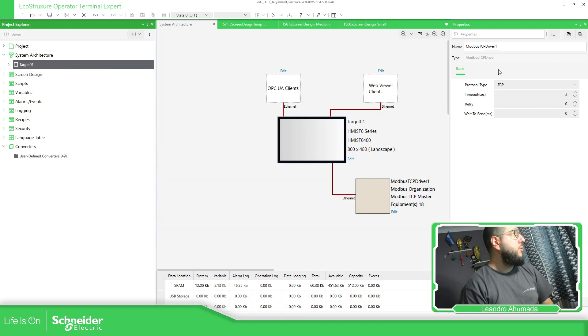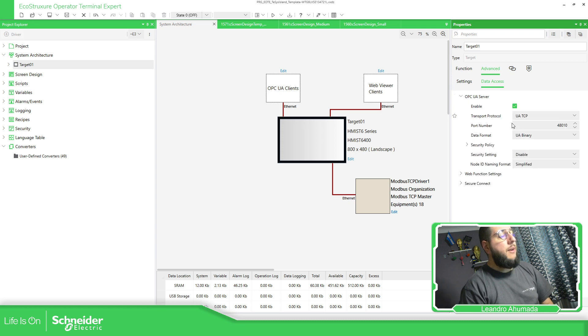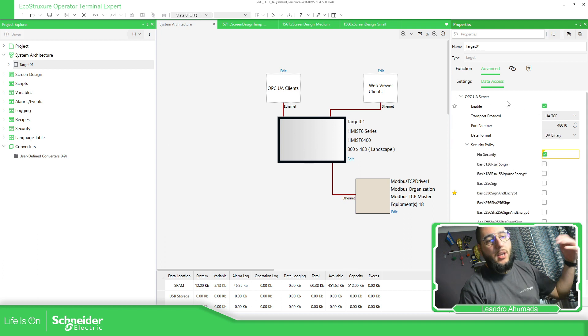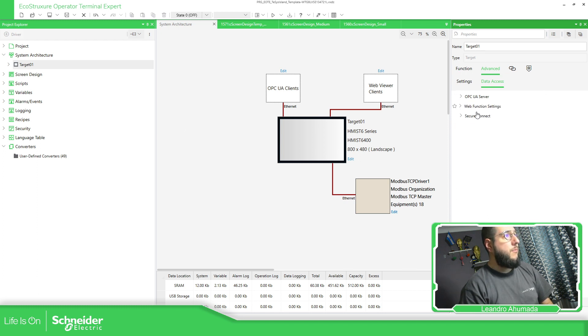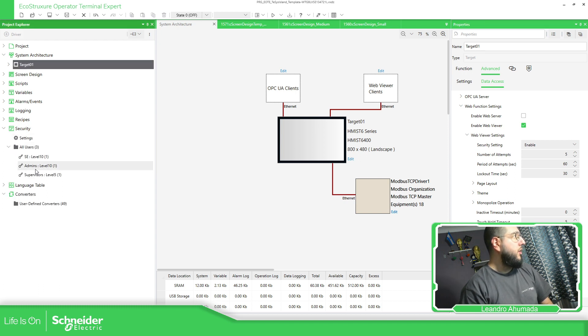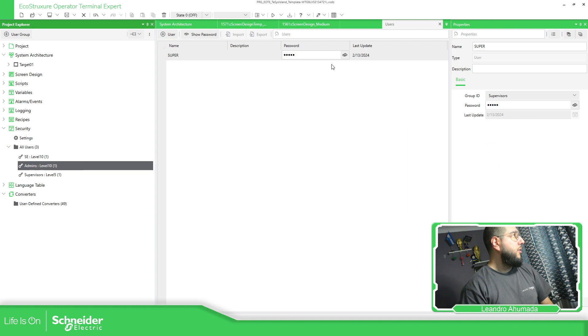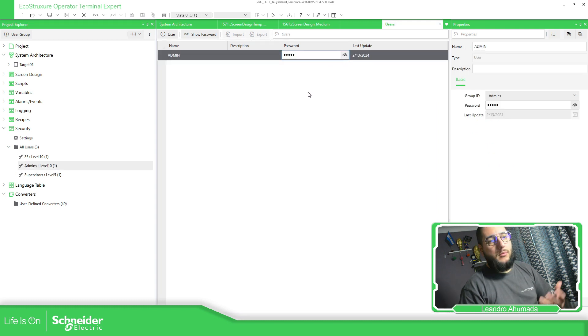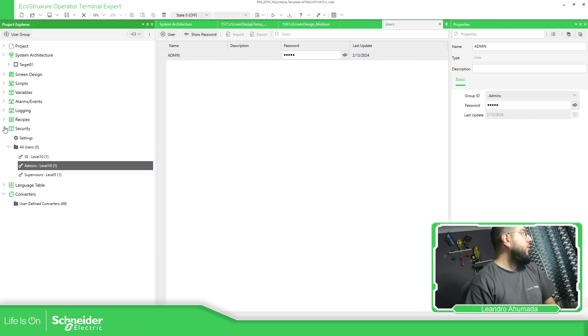Let's take a look at the OPC UA configuration. By default, I haven't configured the security. If you need security or further settings, just open the application and download it. Here is the port for OPC UA, and for the web server, here is the port and the security settings. I've already set up a few user credentials in case you want them — there's also an admin/admin login. If you want something different, you can change it in the security profile.